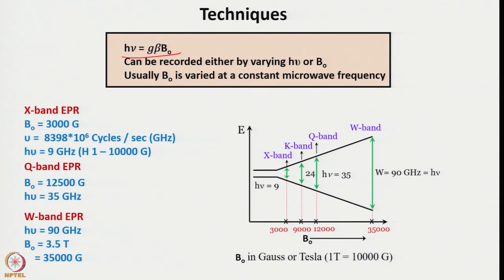In EPR spectroscopy, the energy difference between the two states is given by hν = G·β·B₀. This can be recorded either by varying the microwave frequency hν or B₀; usually B₀ is varied at a constant microwave frequency. For X-band EPR, the typical magnetic field strength is 3000 gauss and ν is approximately 9 gigahertz. For Q-band, the field is 12500 gauss and hν equals 35 gigahertz. For W-band EPR, ν equals 90 gigahertz and B₀ equals 3.5 tesla or 35000 gauss.